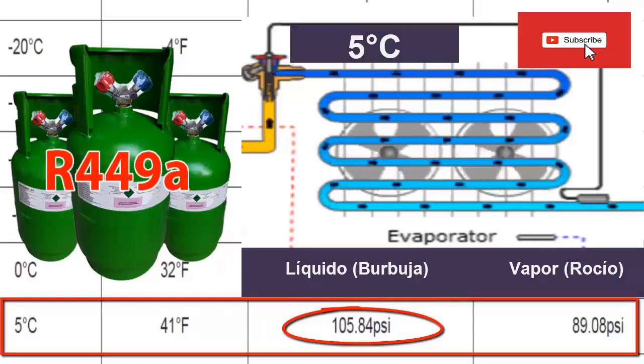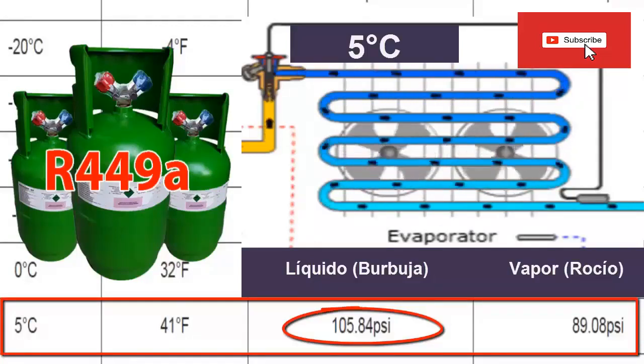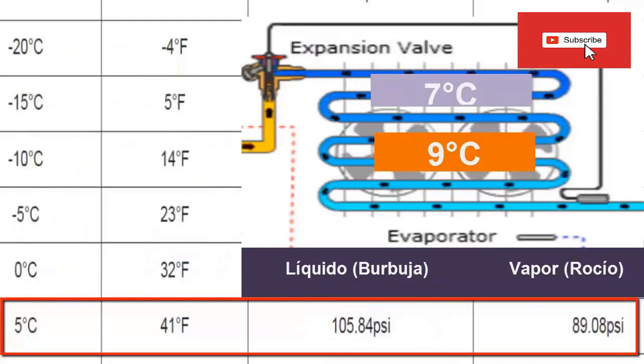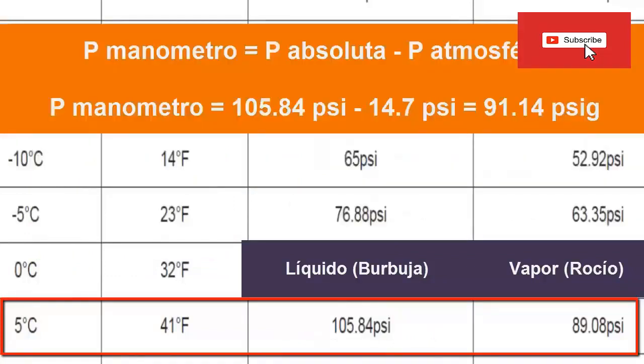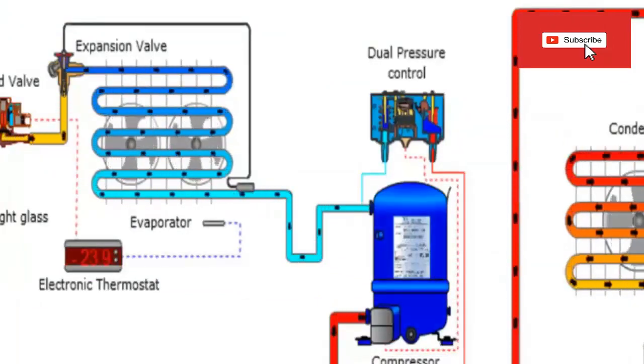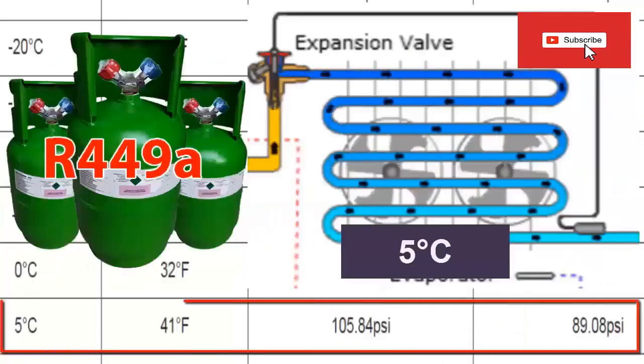Since R449A has glide, even though it is 5 degrees at the inlet, this value begins to increase. Therefore, before leaving the evaporator, when there is simultaneously liquid and vapor, the temperature will not be 5 degrees but will be higher. If we want the 5 degrees to occur not at the inlet but rather at the outlet of the evaporator — that is, when there is pure refrigerant in the form of vapor — then we must work with vapor or dew pressure, in this case with a value of 89.08 psi absolute.